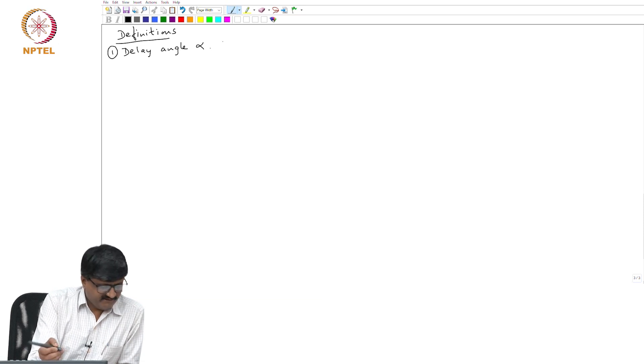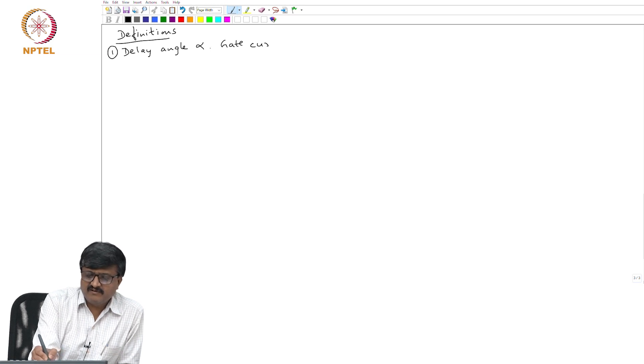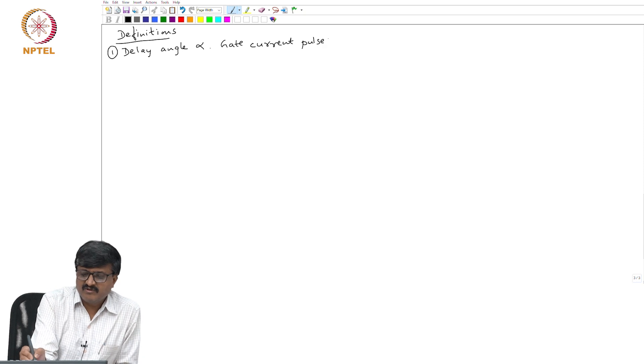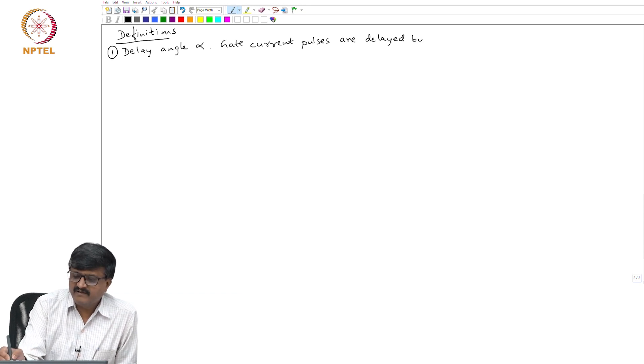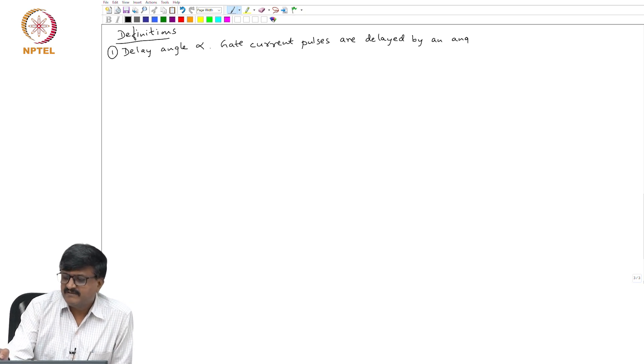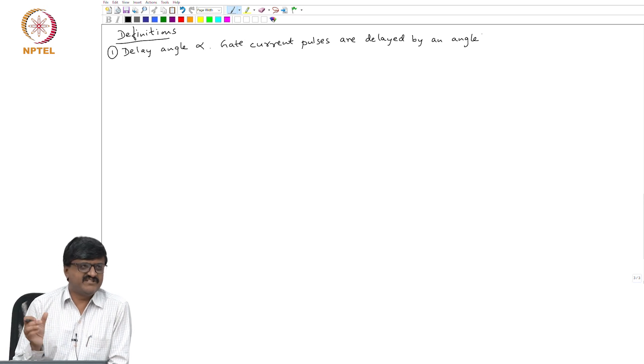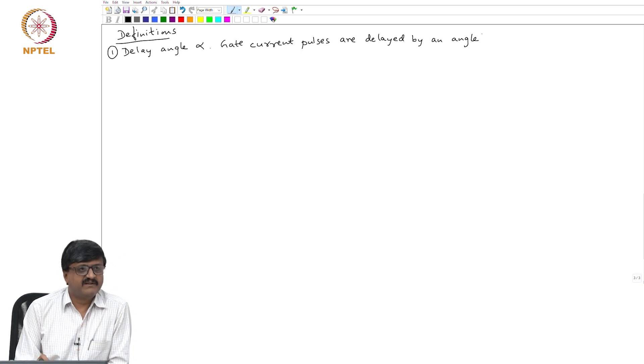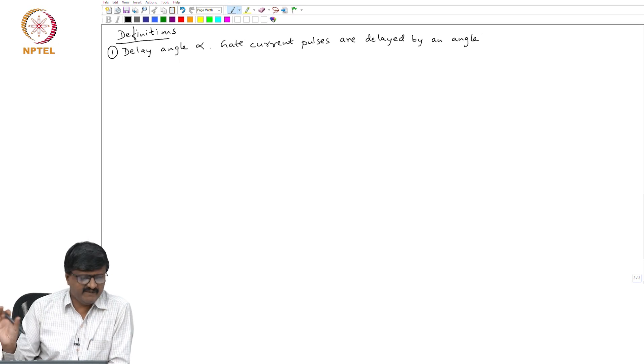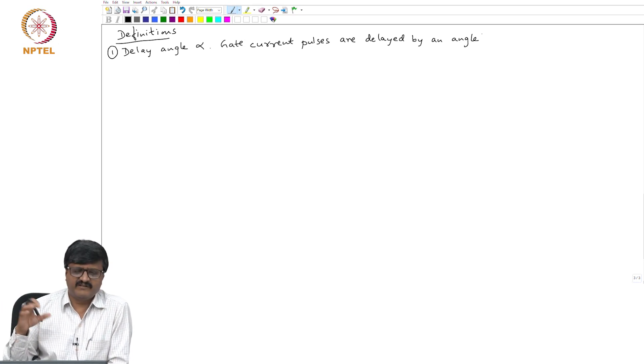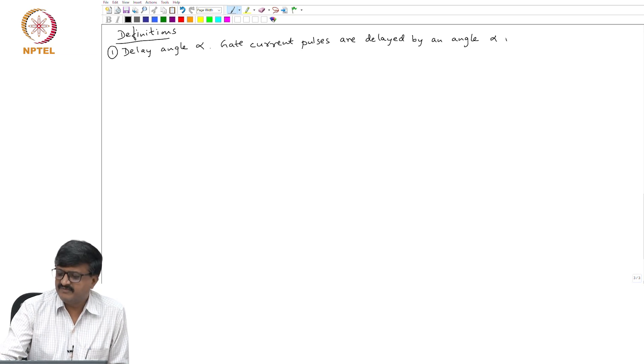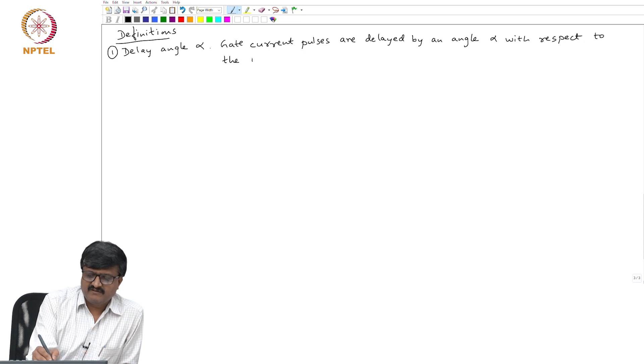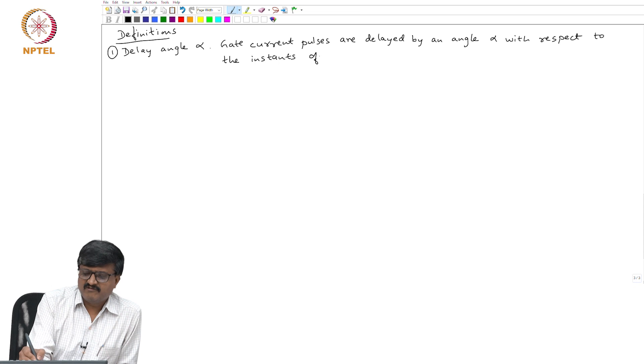The delay angle alpha is defined as follows: gate current pulses to the thyristor valves are delayed by an angle. We use the word 'angle' and the word 'duration' interchangeably sometimes. Normally we do not talk in terms of time; since our independent variable in this course will be angle, we talk in terms of angle only — delayed by an angle alpha with respect to the instant of natural conduction.